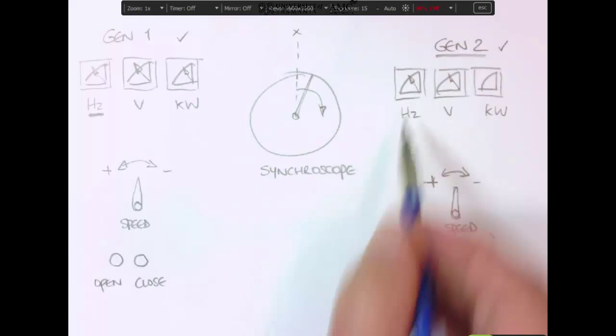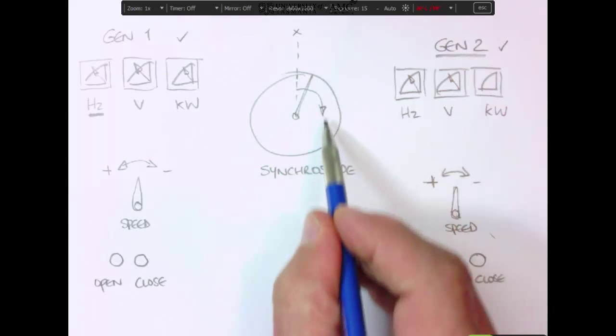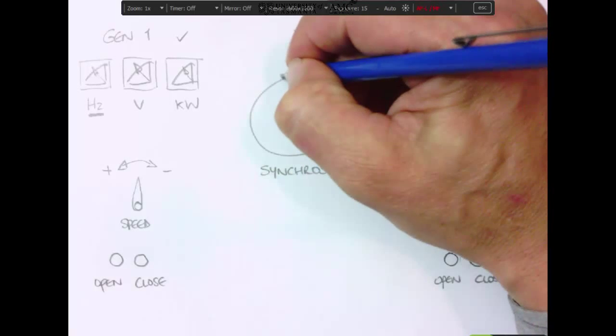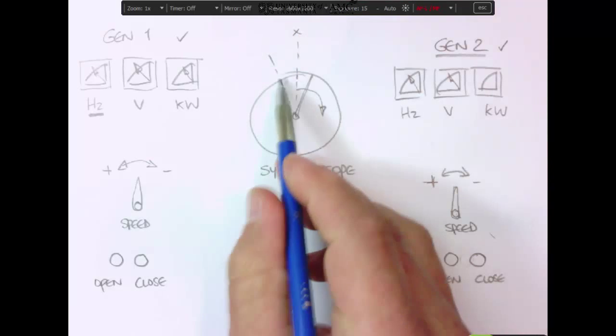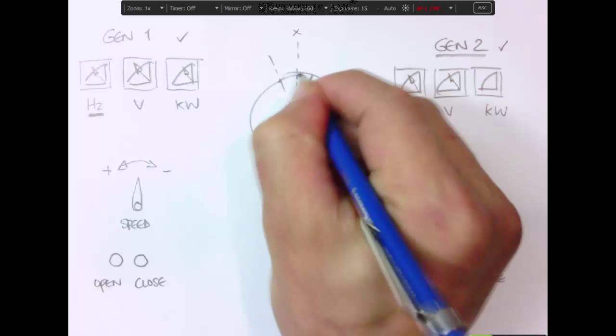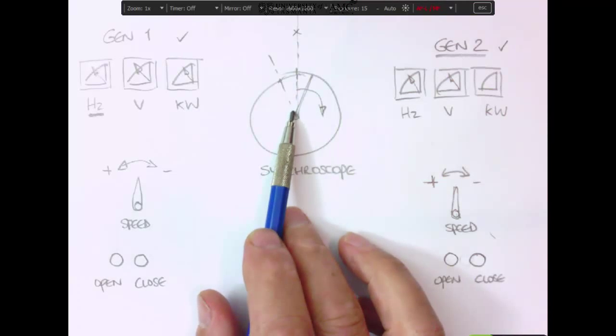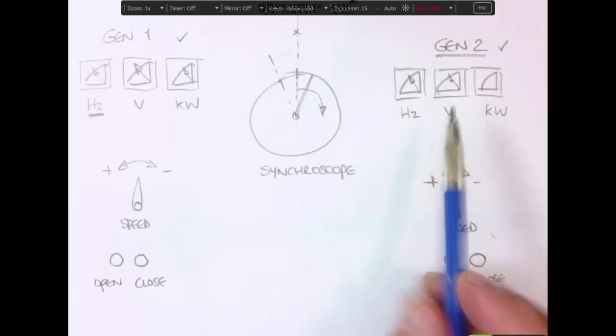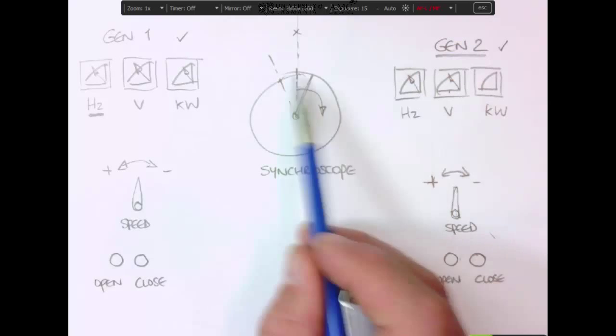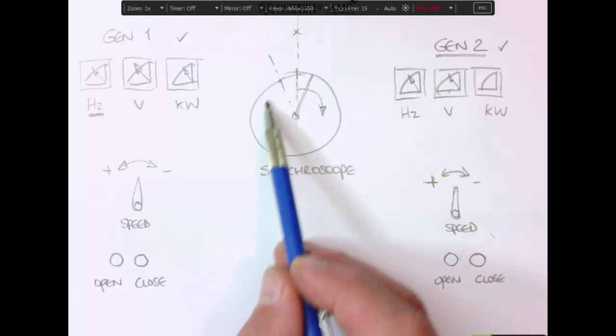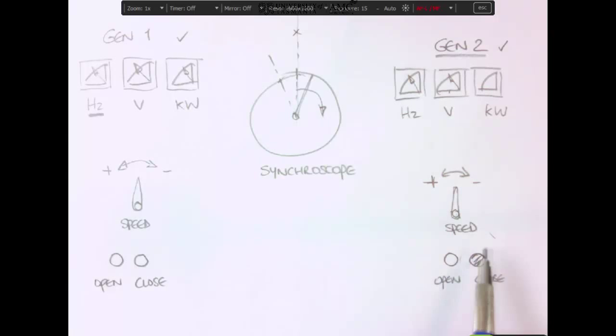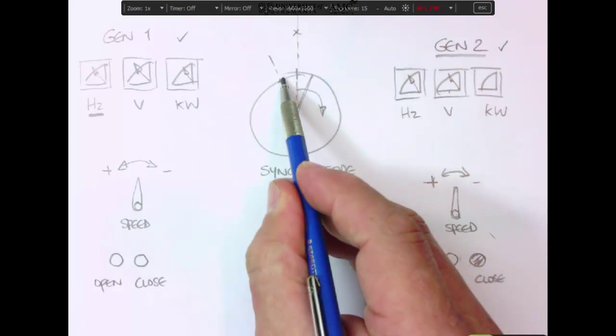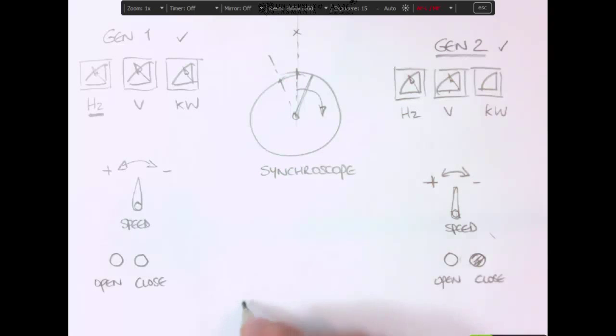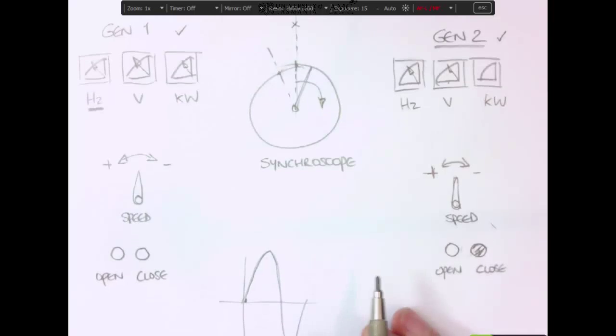Now, when we start, we increase the speed slightly on the incoming machine. It rotates slowly in the clockwise direction. And the accepted practice is to bring it online at about 5 minutes to 12. That way it's got time to catch up, and it should be perfectly synchronized at the 12 o'clock position. So all we do is ensure that our voltage is right, set our frequency so that we get slightly faster rotation in the clockwise direction, and then we close our circuit breaker for the incoming machine at about 5 minutes to 12, and that should bring our 3 phases in sync with one another so that they start at the right phase at the right time and they're in sync with each other.